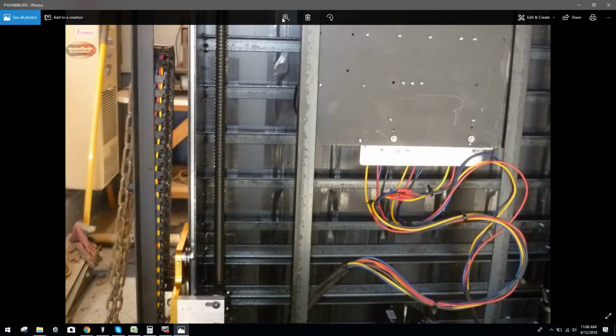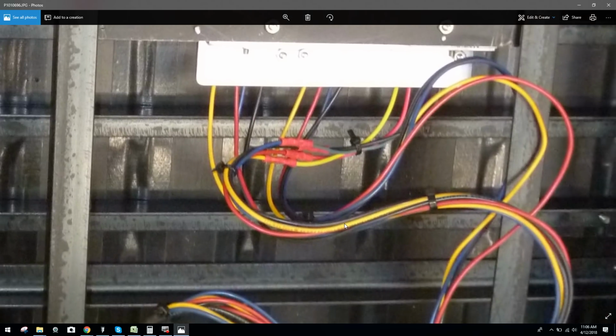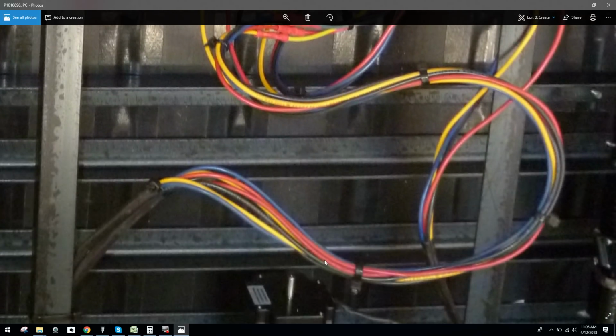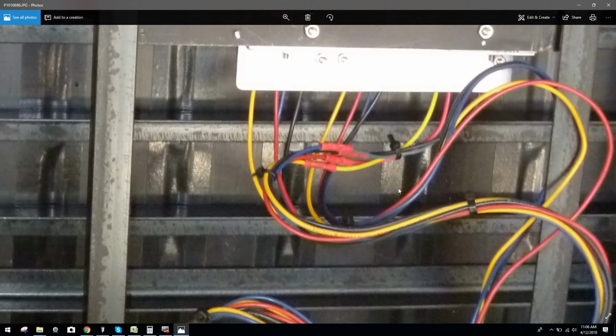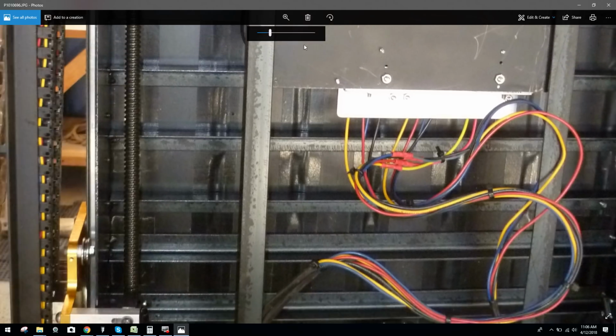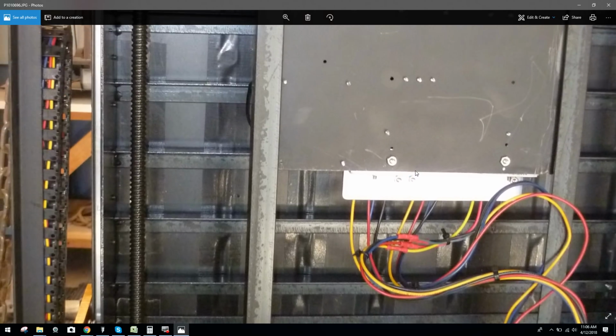Look at the motor cables. None of that. We'll zoom in real close because I want to make sure that everybody can see this. None of this is shielded at all. Look, and you can see here where the conductors are going into the casing. You don't see any aluminum or any metallic color whatsoever. So I can tell you right now, there's definitively no shielding being used on this system at all. When we see that, you can guarantee that this system is playing with fire.